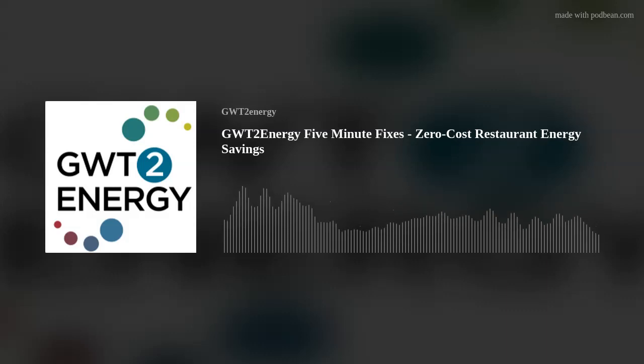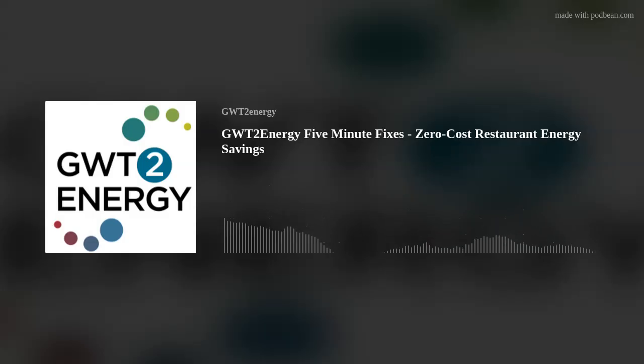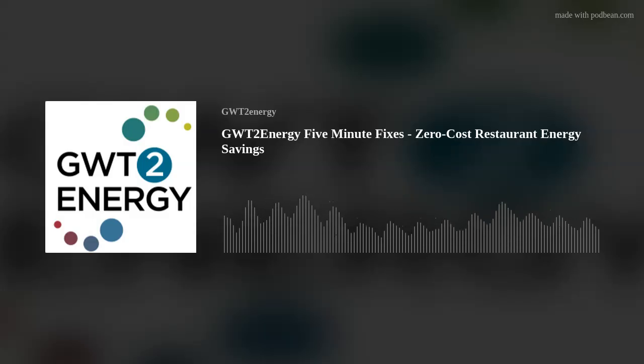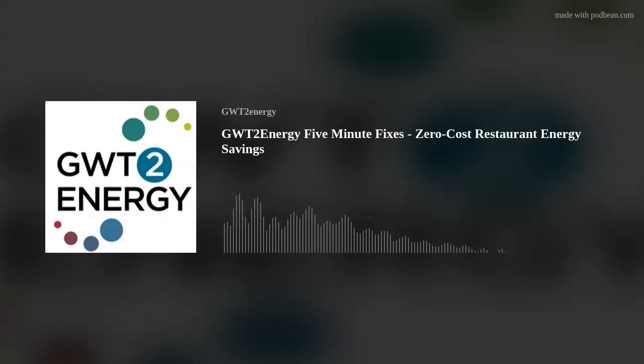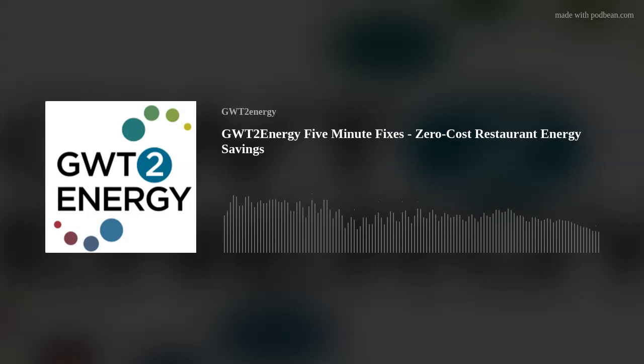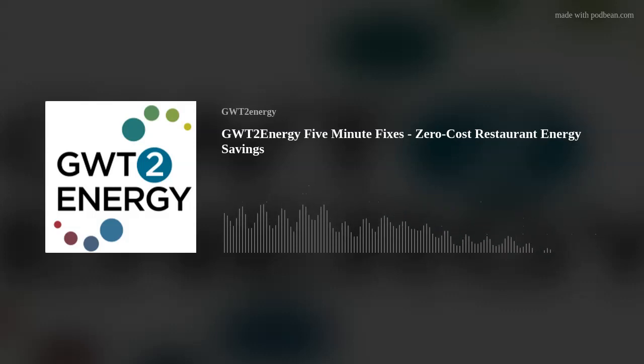Okay, I follow. But by letting the temperature drift up to 85, you shrink that difference. The AC compressor barely runs, if at all, for 8 hours. And then you just hit it hard an hour before opening. Yes, the compressor runs intensely for 60 minutes, but it takes way less total energy to cool the building from 85 to 75 in one focused blast than it did to perpetually maintain 70 degrees for 8 long hours. You got it. You trade long, low, inefficient runtime for short, high, efficient recovery time. That is a phenomenal insight. It totally transforms HVAC from a static cost into something you can actually schedule.